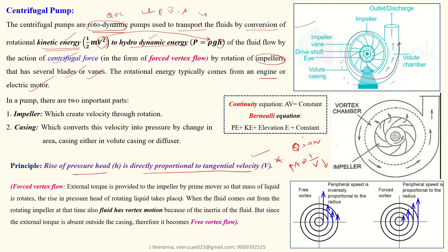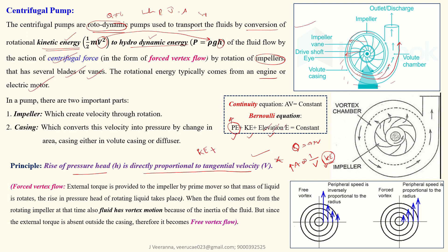The velocity, which represents kinetic energy, increases toward the casing due to centrifugal action of the impeller. As the area increases toward the outlet, from Bernoulli's equation, pressure energy plus kinetic energy plus elevation energy is constant. If elevation is neglected, when kinetic energy (velocity) reduces, pressure energy automatically increases.